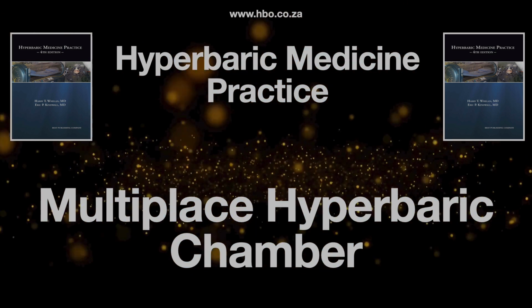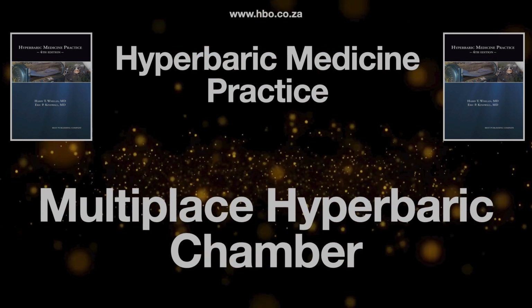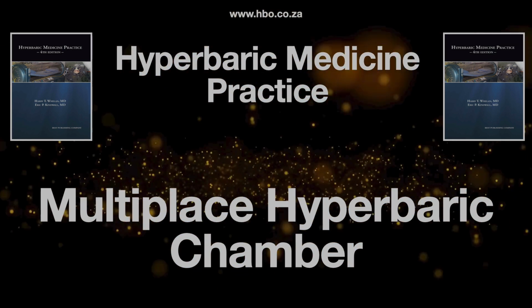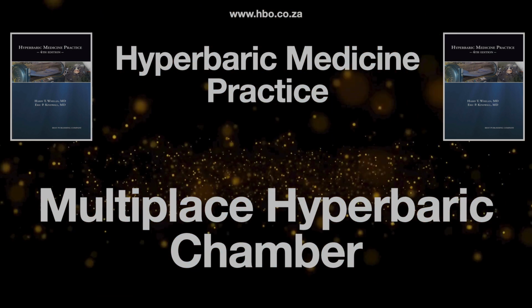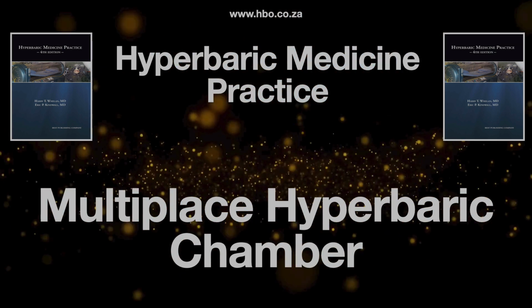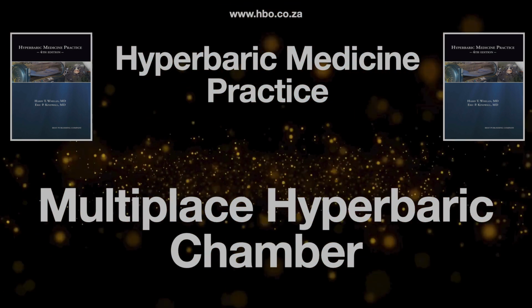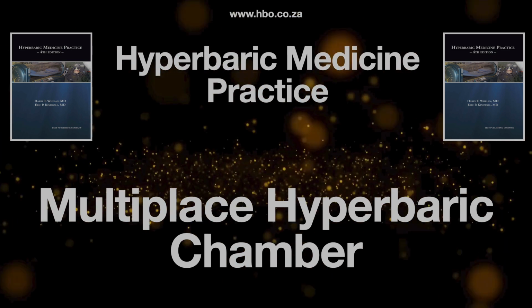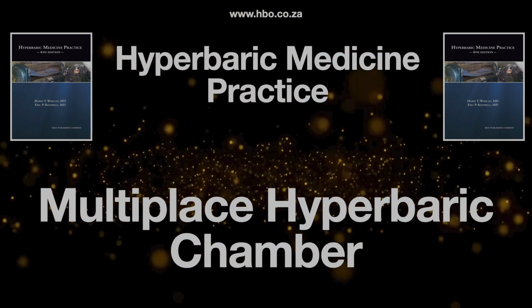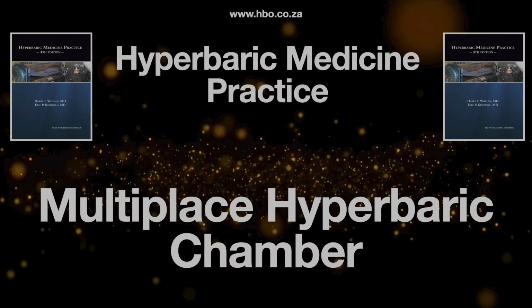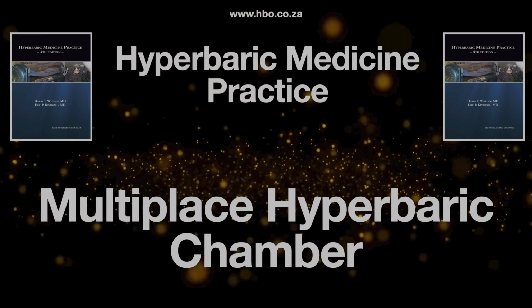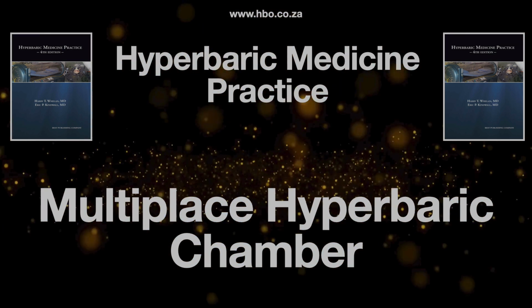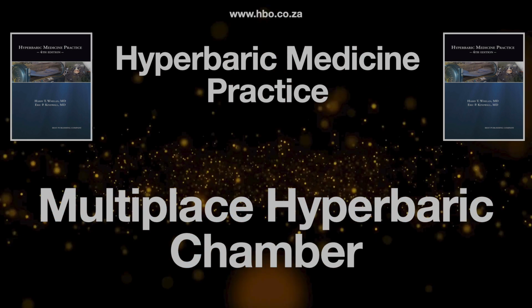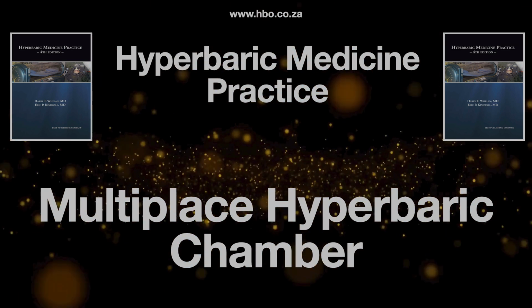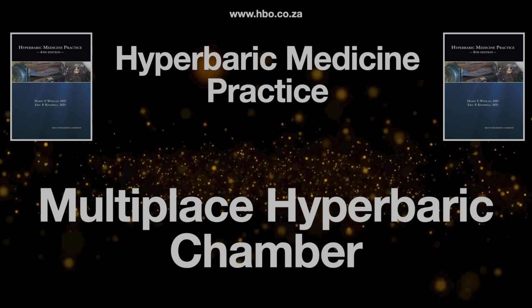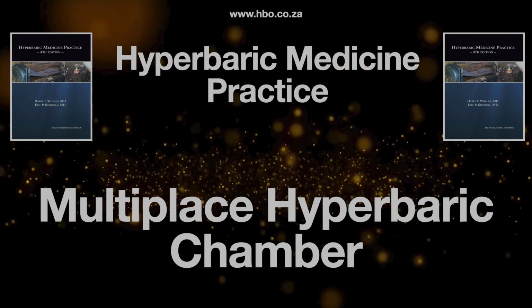What are the key things they look for in hyperbaric certified devices? Several vital points. First, the device has to maintain its settings accurately despite the pressure changes. It can't drift. Right. Second, it has to stay fully functional, adjustable throughout the whole treatment. Third, if it's battery-powered, it needs serious autonomy, like enough power for at least 1.5 times the planned treatment length, just in case. And a buffer. Yeah. Alert thresholds on monitors might need adjusting too because of how oxygen behaves in the blood under pressure. And a basic principle is always minimize personnel and equipment inside whenever possible. Keep it simple. Exactly.